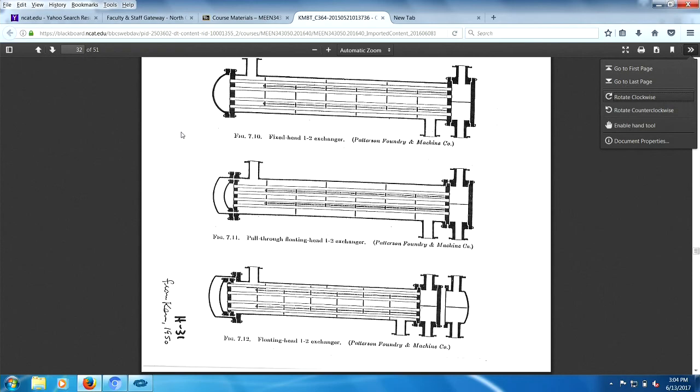Oh, when I was an undergrad, we had a heat exchanger. It was pretty funny as hell. It had these baffles in there. And what happened is the baffles were so bad, we injected dye on the shell side to see what would happen. It was a visual glass shell. And we injected the dye, and the dye went right through. It didn't go across like that. It didn't do that at all. That's because the baffles were poorly designed. There was a lot of leakage in there, baffle leakage. In other words, flow bypassed the baffles. It'd go through here, go around the tubes. That's not good.